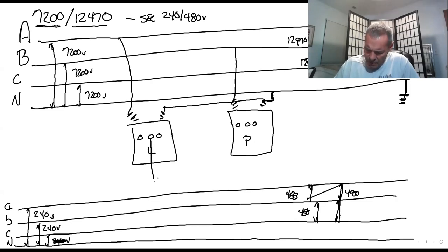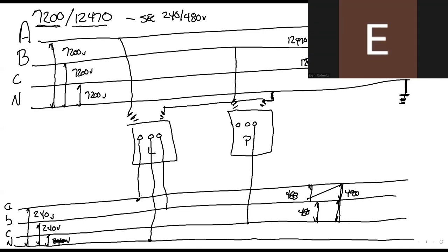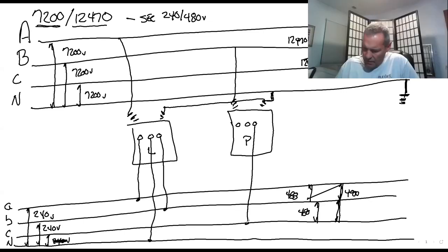I'm going to draw my neutral line in first. Make a connection. Then I'm going to work left to right and go by the alphabet. A, B, use the far right-hand bushing of this transformer, C. So I've covered all three of the hot legs. The only thing that remains is I need to tie my two transformers together with tie-in bus.